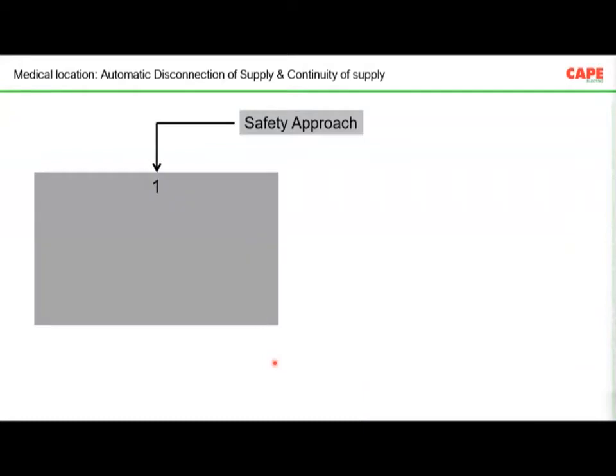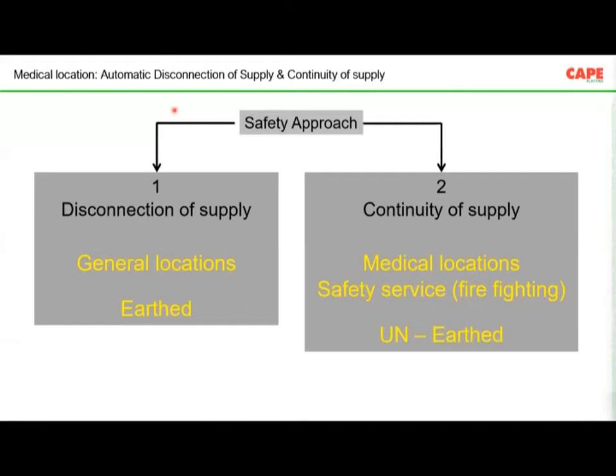We always have a confusion: what exactly is the TN system or TT system? Because for safety, the first point is what kind of system earthing you are doing. Now, with respect to safety, system earthings are classified into two. The first one, on the left side, is an electrical installation where safety is achieved by disconnection of supply. Disconnection of supply in the sense that, in case of any fault, the supply must be disconnected within a certain time.